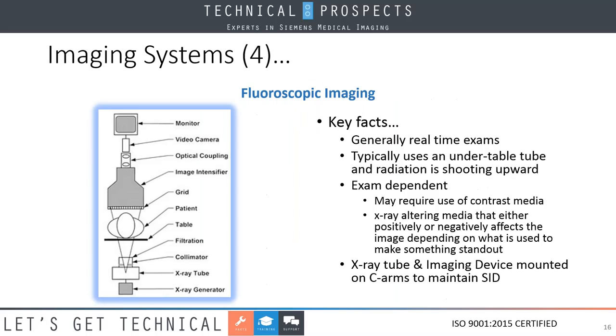So moving on from here, let's take a look at some key facts about fluoroscopic imaging. I've talked about some of them. You have a picture here showing that the X-ray tube is on the bottom, shooting up through the patient to the image intensifier and the whole sequence of the imaging chain. With today's portable C-arms that rotate, you may have the X-ray tube on the top. Some X-ray systems today are actually designed for fluoro using an over-table tube shooting down. That's all fine, but the imaging chain is still the same.